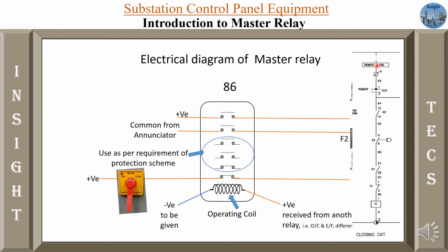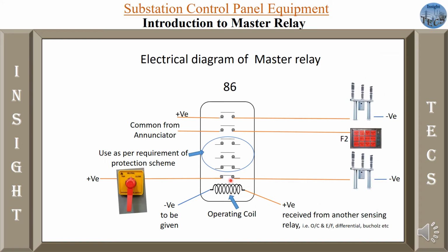So unless and until the breaker is closed and this is operated, you have to reset the master relay whenever the breaker trips, and only then will you be able to close it. Okay, so that is how the wiring is done for the interlock in the circuit breaker.